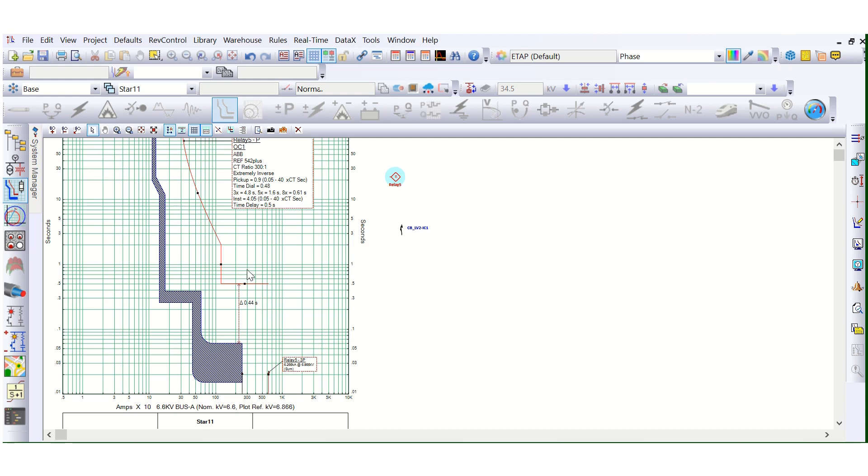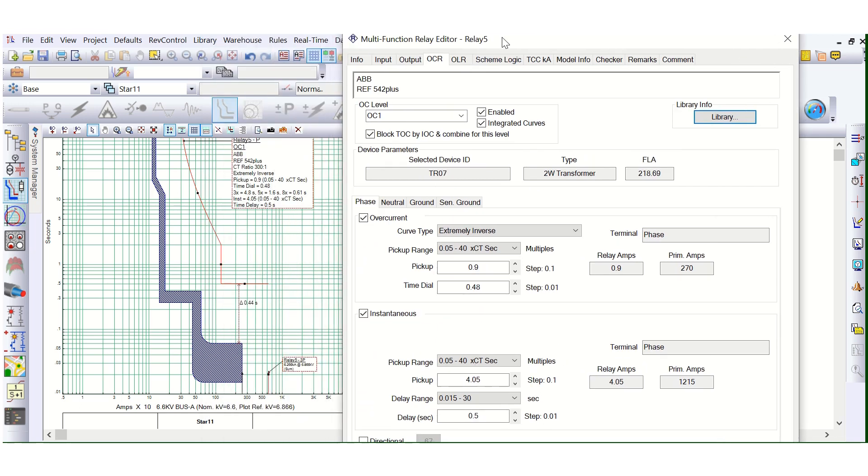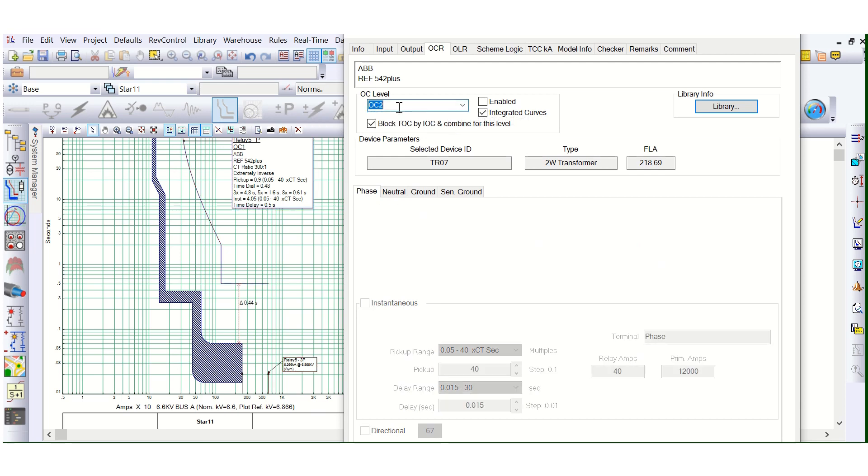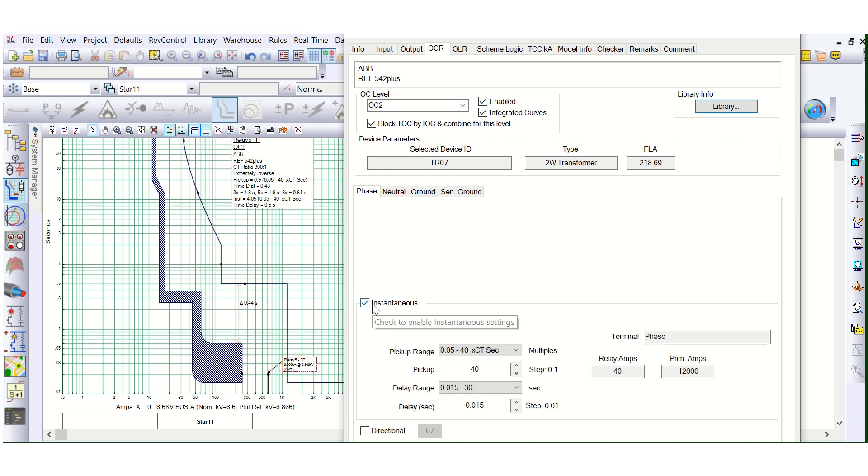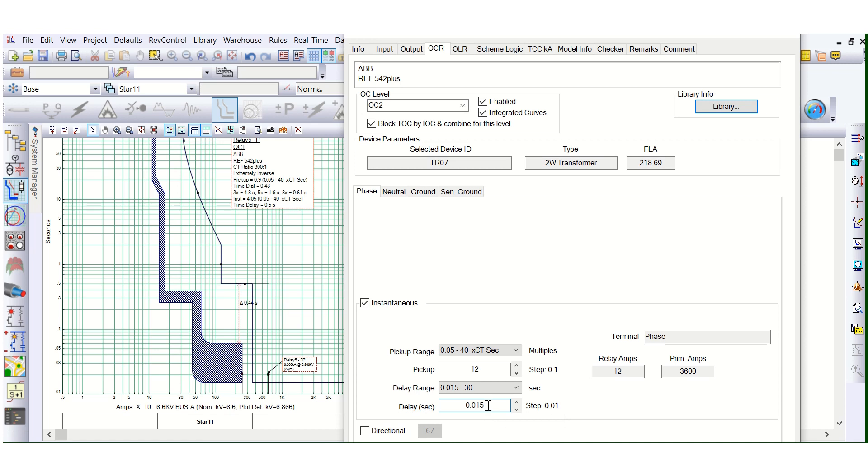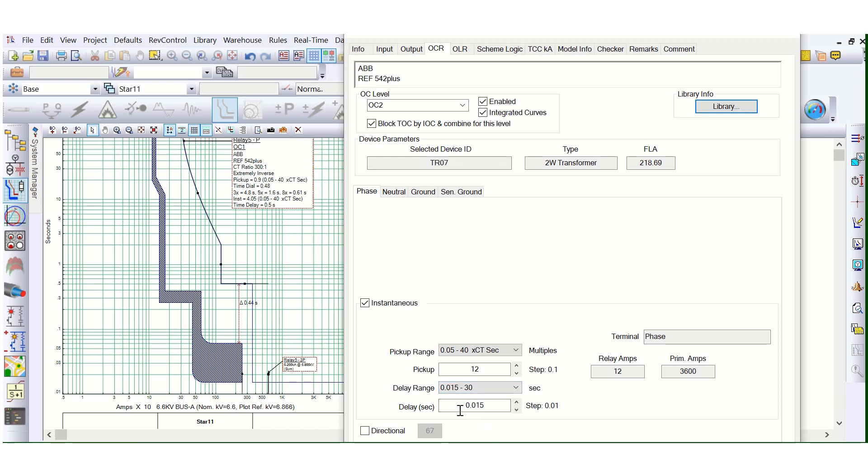For this case also, we can do this for the sake of example, for the sake of clarity. We'll go here in the editor and go to this OC2, enable this instantaneous, check this box and here you can see, let's say this is 12, that means 3600 primary amps tripping and this is the time delay. What is the delay? There is no intentional time delay. This is the minimum time required for the relay for the instantaneous operation. So this time we have to give, we cannot make it 0, because the delay range is starting from here, you can see 0.015 to 30, that means the minimum setting we are giving, that means there is no intentional time delay.